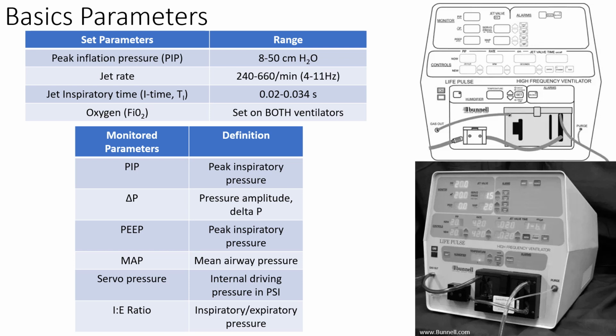The high-frequency jet ventilator is unique because it utilizes high ventilator rates, small tidal volumes, and passive exhalation, and functions in tandem with the conventional ventilator. The desired oxygen is set on the jet and conventional ventilator, so it is important to ensure that the set oxygen on both machines match. This method of mechanical ventilation can enhance carbon dioxide elimination and utilize low airway pressures to minimize the risk of lung damage.